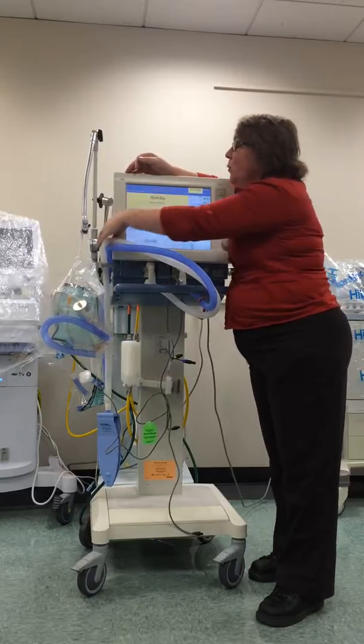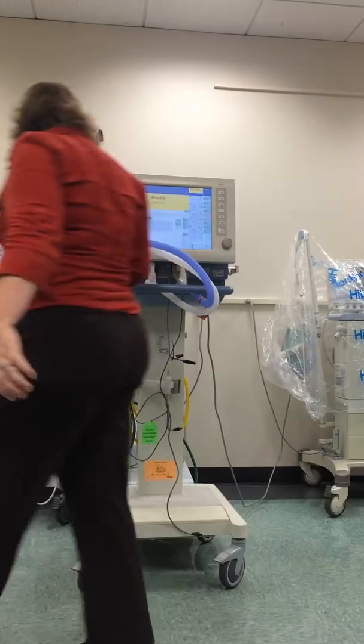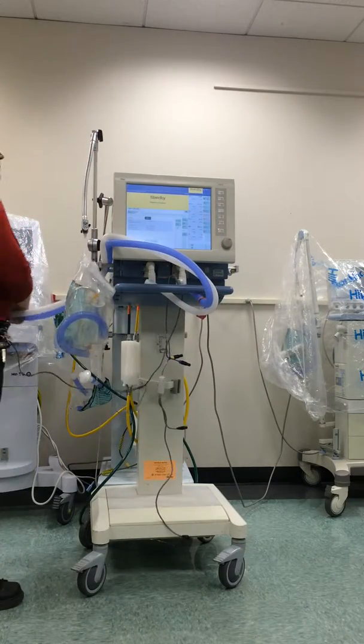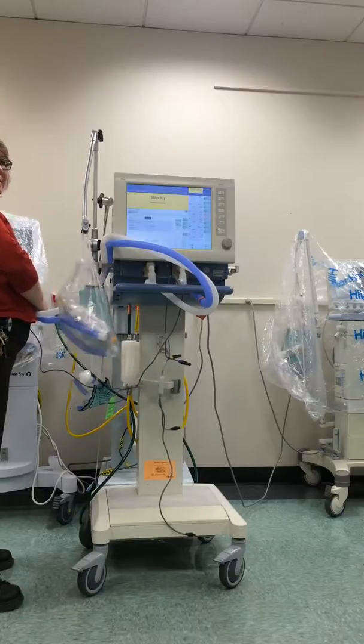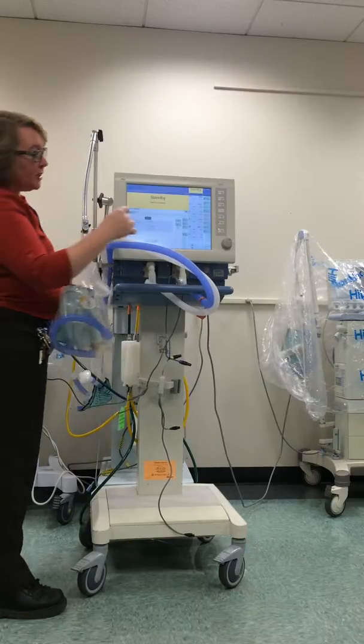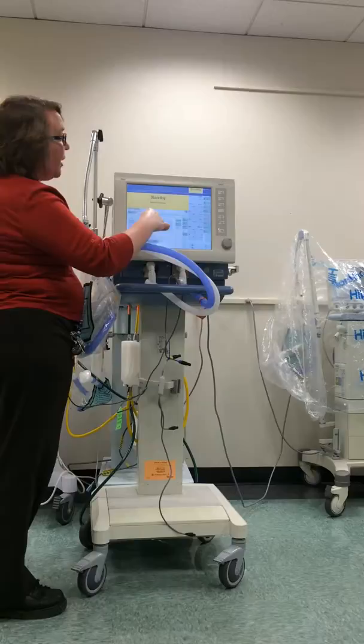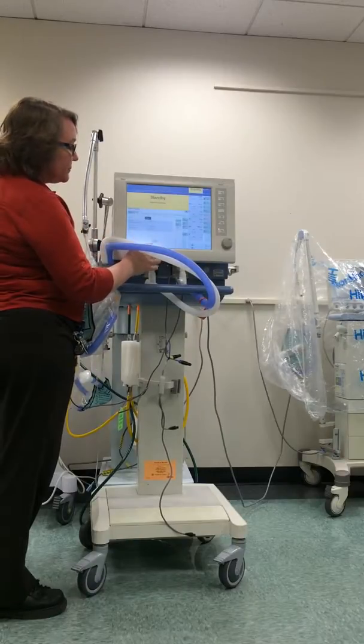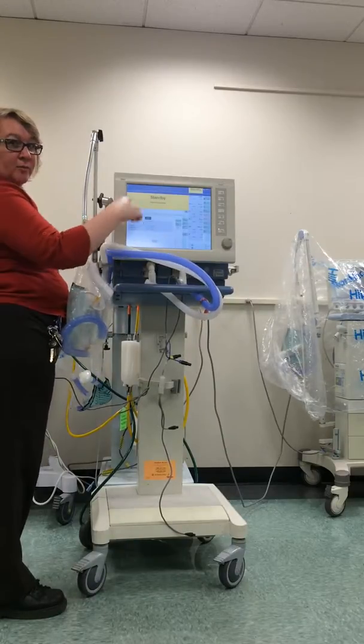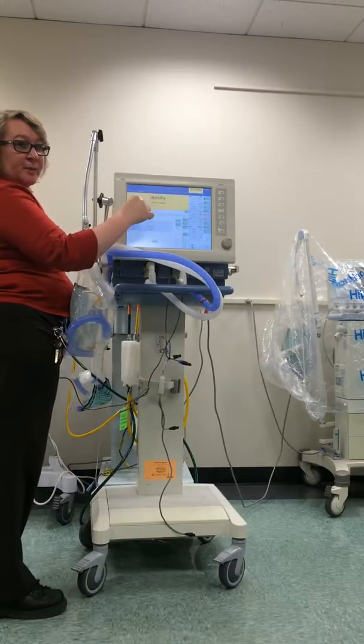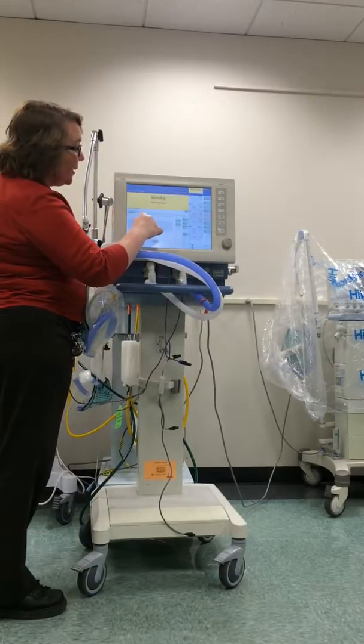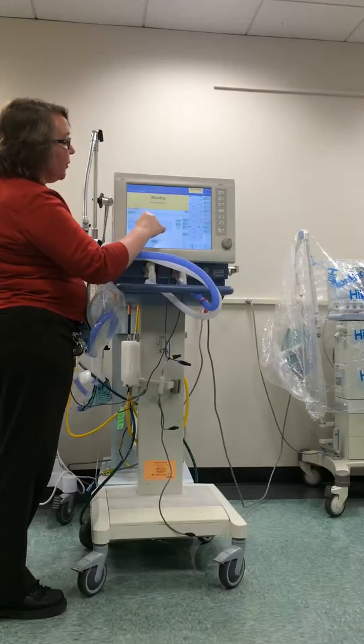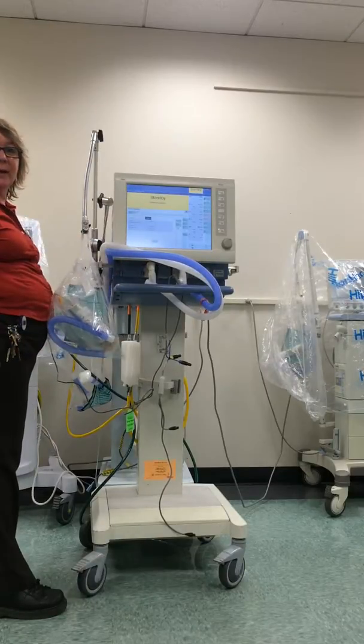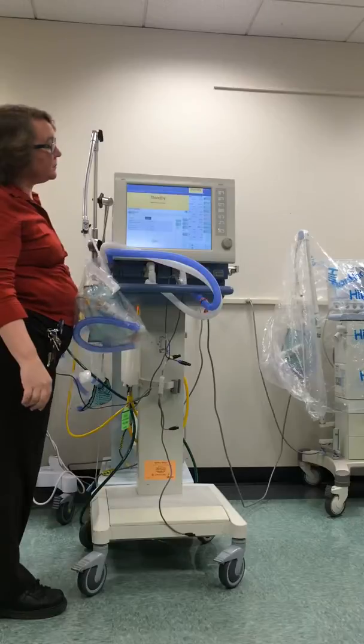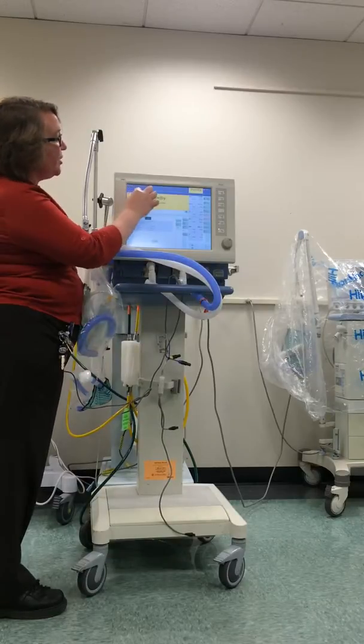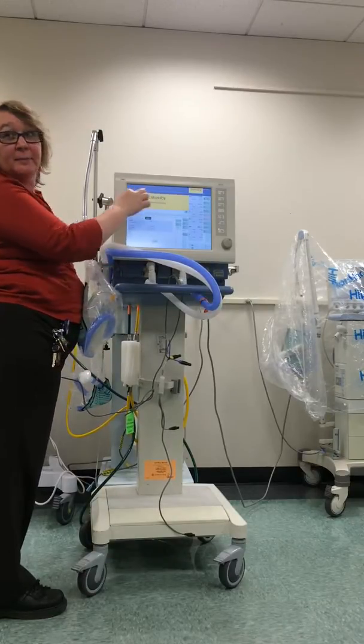And it's going to say seal Y piece, confirm with yes. So you want to block your hand over it. And what it's going to do is make sure that no air is leaking out of your circuit. You'll see this number up here if there's a problem. So I'm going to hit yes. And you'll hear air going through here. It says check is active, please wait. And then you want to see these numbers at around 0. If you're seeing in the thousands, it's not going to pass. So just watch up here. Once nothing is up there again, it's done.